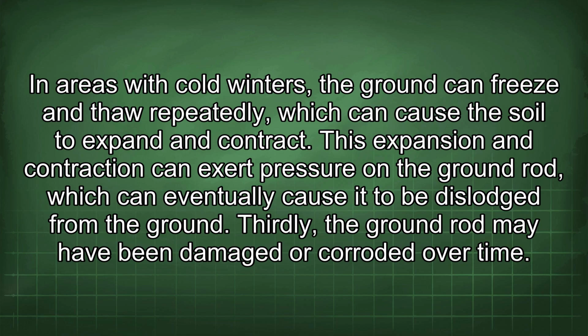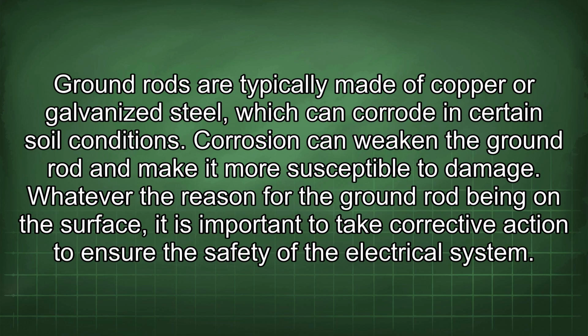Thirdly, the ground rod may have been damaged or corroded over time. Ground rods are typically made of copper or galvanized steel, which can corrode in certain soil conditions. Corrosion can weaken the ground rod and make it more susceptible to damage. Whatever the reason for the ground rod being on the surface, it is important to take corrective action to ensure the safety of the electrical system.